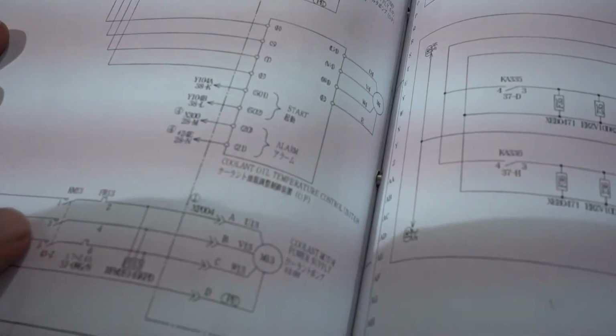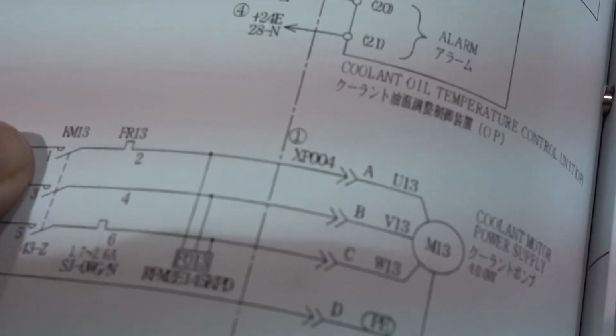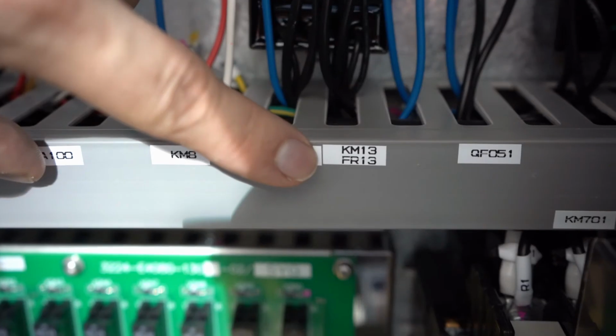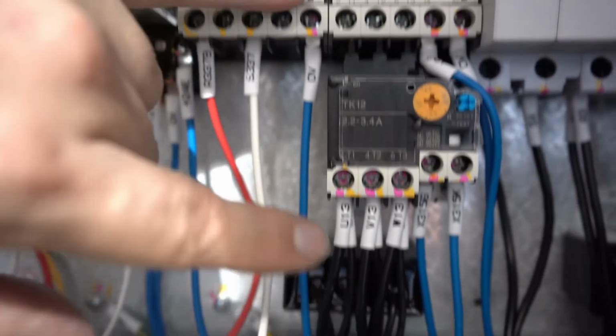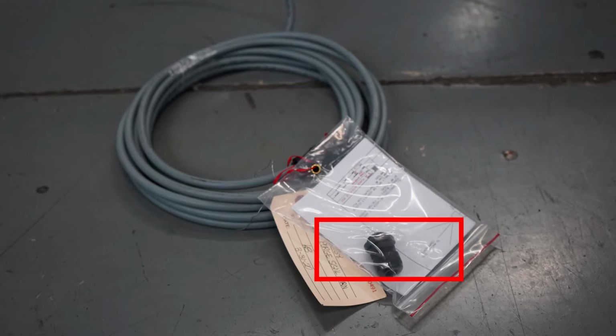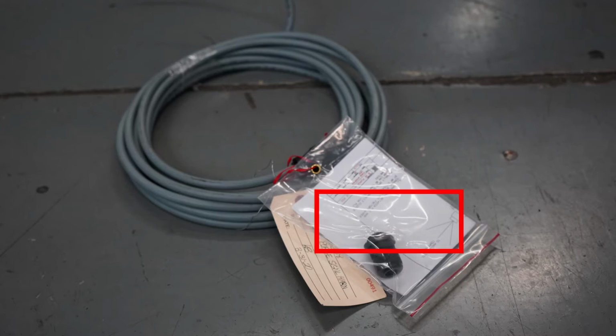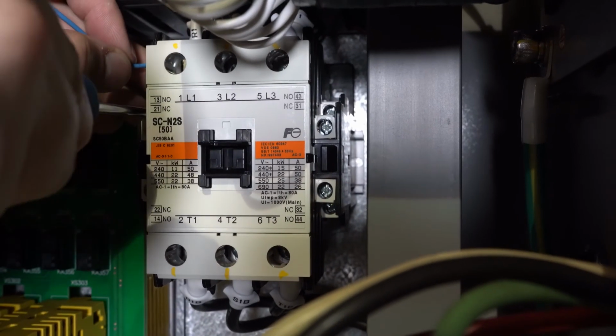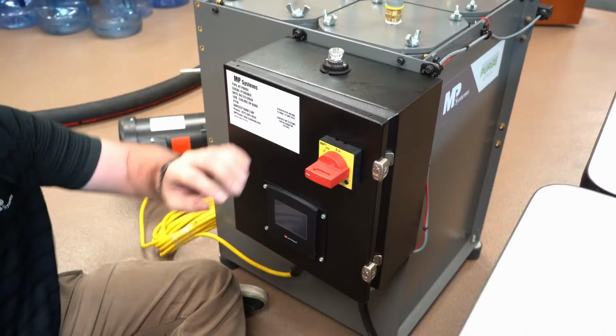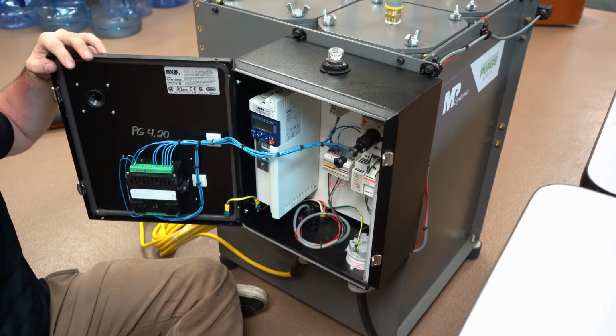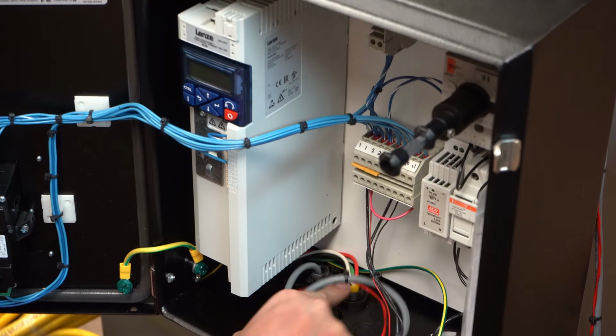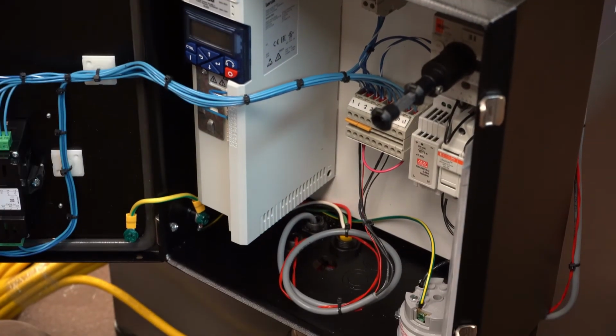To install the purge interface, you'll need to find the dry contacts. Once you have found the dry contacts, refer to the schematic attached to the interface cable and attach the wires accordingly. Next, the purge side of the cable can be connected by opening the electrical cabinet and removing the plastic plug in the bottom of the panel.